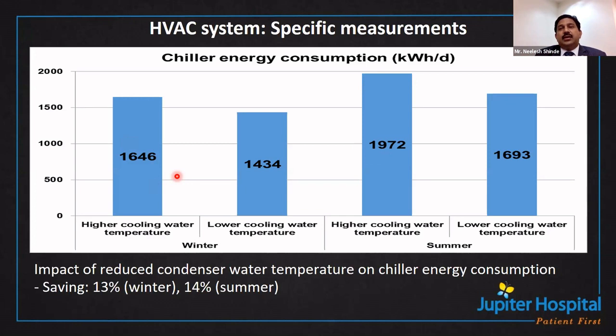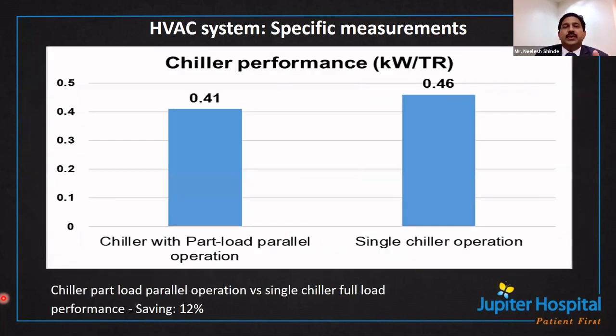So what we have done is, if we reduce the condenser inlet temperature from 27 to 23, these are the results. Please understand very clearly that if you are just playing around with the condenser water temperature and reduce it that much, then you can achieve a saving of 13% in winter and 14% in summer. This is a huge saving that can happen just by controlling the condenser water temperature.